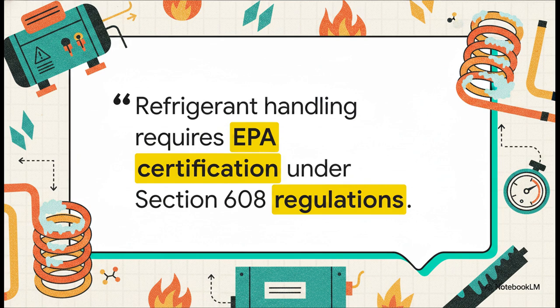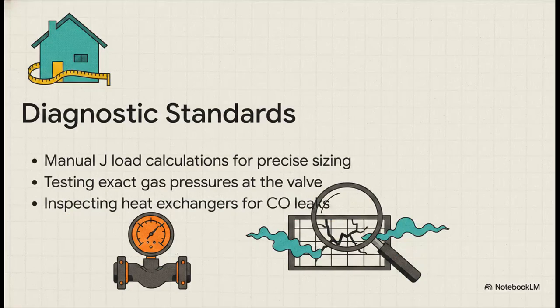Modern systems, especially those using R410A refrigerants, require incredibly precise measurements. Adding refrigerant isn't just topping off a gas tank. It requires exact calculations based on line length, outdoor temperatures, and specific subcooling and superheat measurements. If you overcharge it, you destroy the compressor. Undercharge it, and the coils freeze solid. It's a delicate balance. To really protect your home, professionals have to rely on hard data.